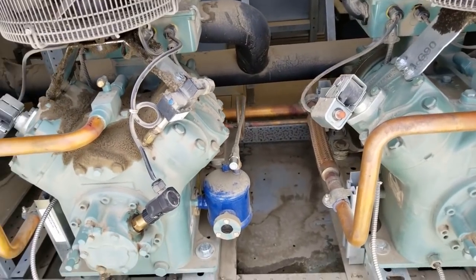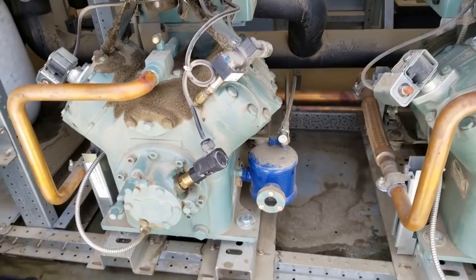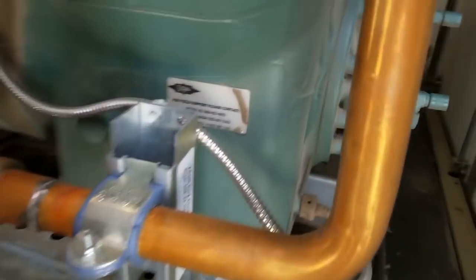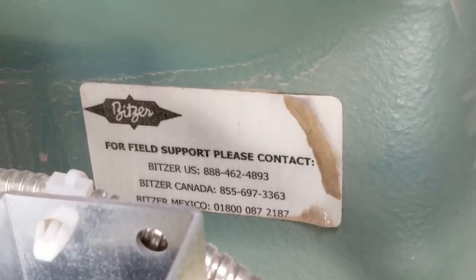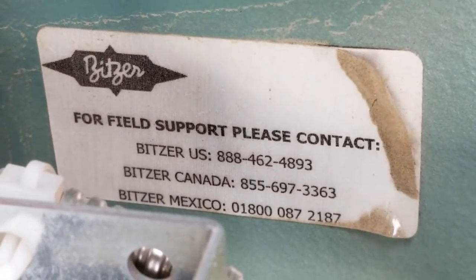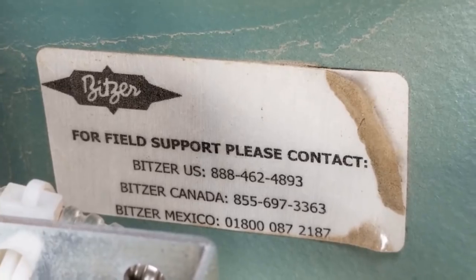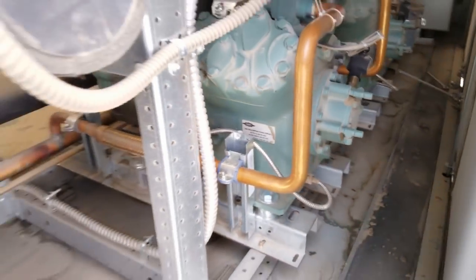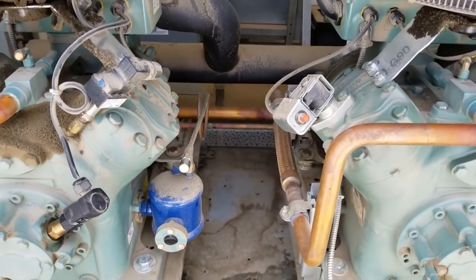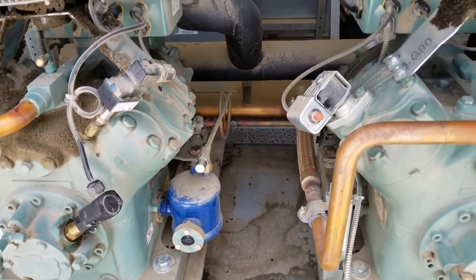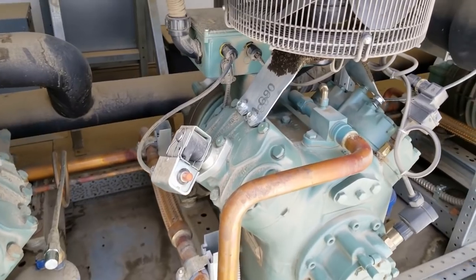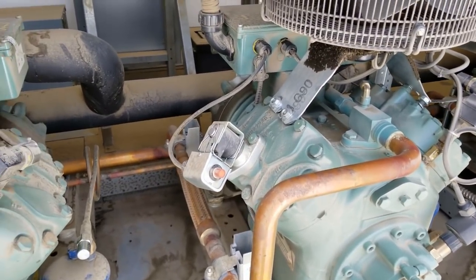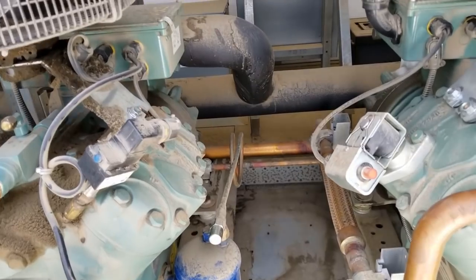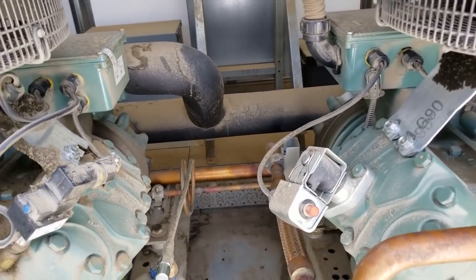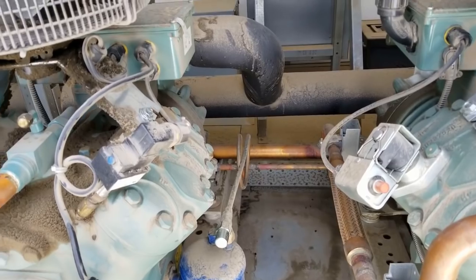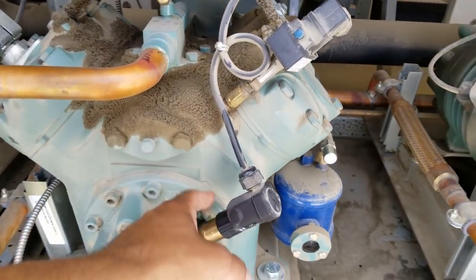Okay guys, this is what happened. I put everything back together. Earlier I called that phone number, if you can read it - I called the US one. That was earlier when I got here, and they called me back just now. What was going on, remember I was telling you guys the compressor was coming back a little too rich, too much flood back coming to the compressors. And 99% of that's going to be my issue, washing out my oil or causing the differential to mess up on this Delta P.